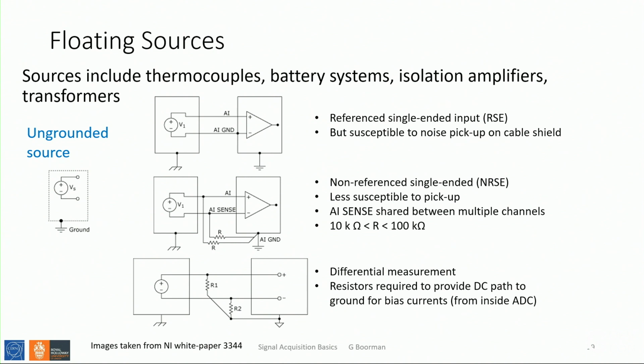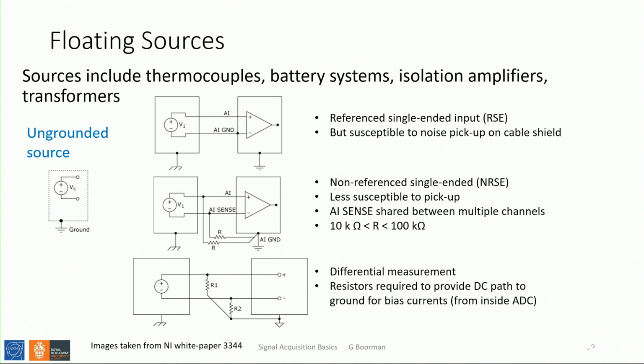Again, differential measurements: if you want to avoid most problems with noise, ground loops, pickup and so on, differential measurements are the ones to do. It's set up similar to the analog sense, but whereas AI sense is used for multiple channels referenced to ground, here you're using true differential measurements. The disadvantage is you can only use half the number of channels of your ADC card. You have to trade off number of channels versus how much noise or induced current you can withstand.